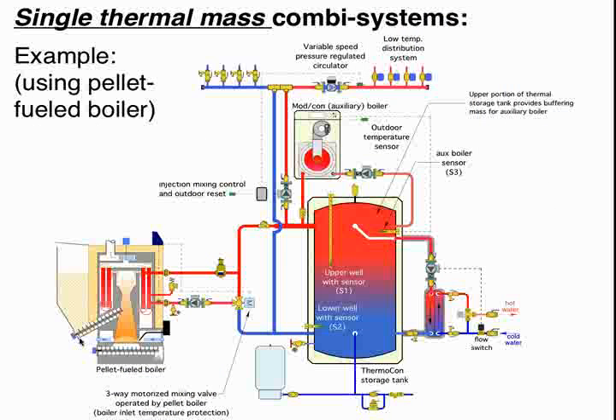Okay. Here's one way that you could set something up like that. This tank is actually buffering space heating, and it's also providing domestic water. I set this up around a pellet-fired boiler. With a pellet-fired boiler, we have to have boiler protection. We have to protect that boiler against sustained flue gas condensation. So that's what the mixing valve is here. This is basically to allow that circuit to warm up as quickly as possible, get the boiler's heat exchanger above the dew point of the flue gases so we don't cause corrosion inside the boiler or the venting system.